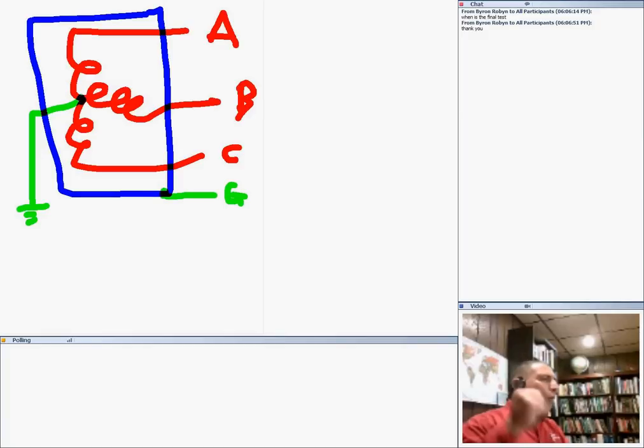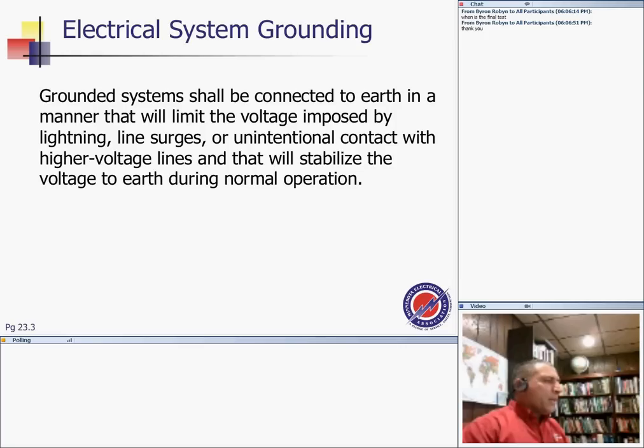You have to take the windings of the transformer to Earth for the system to be grounded. Just because you have an equipment grounding conductor does not mean the system is grounded. This is an equipment conductor. The system is not grounded if you only have an equipment grounding conductor. You have to take the winding directly to Mother Earth, like you can see. Okay, question about this? Because this is the most confusing thing when people talk about grounding.